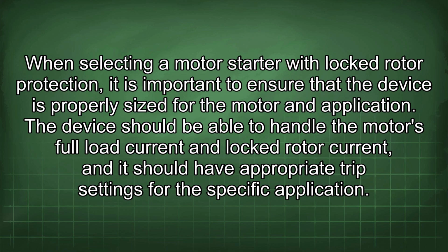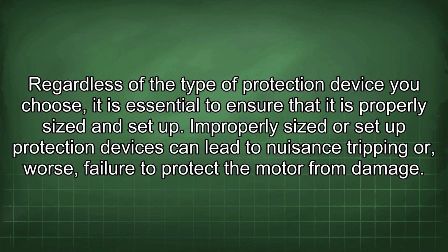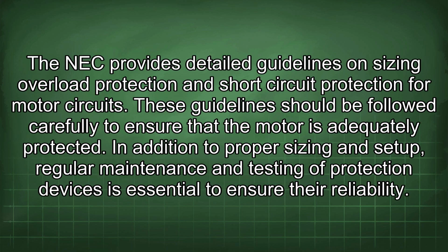The device should be able to handle the motor's full load current and locked rotor current, and it should have appropriate trip settings for the specific application. Regardless of the type of protection device you choose, it is essential to ensure that it is properly sized and set up. Improperly sized or set up protection devices can lead to nuisance tripping or, worse, failure to protect the motor from damage. The NEC provides detailed guidelines on sizing overload protection and short circuit protection for motor circuits. These guidelines should be followed carefully to ensure that the motor is adequately protected.